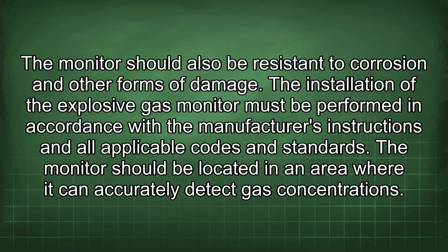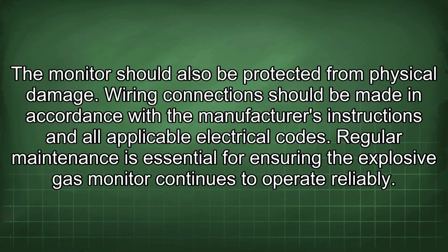The installation of the explosive gas monitor must be performed in accordance with the manufacturer's instructions and all applicable codes and standards. The monitor should be located in an area where it can accurately detect gas concentrations. The monitor should also be protected from physical damage. Wiring connections should be made in accordance with the manufacturer's instructions and all applicable electrical codes.